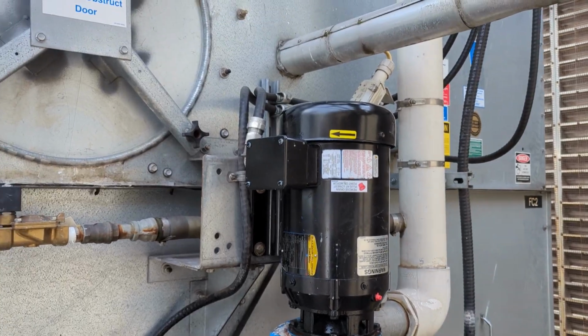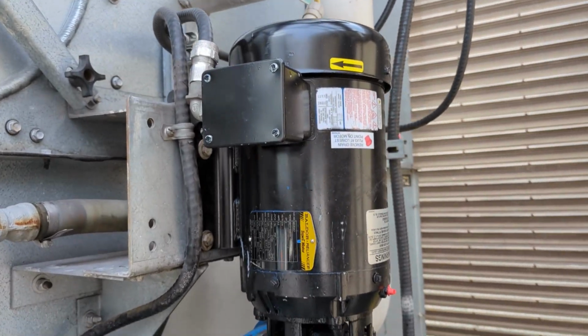We also got back to the cooling towers we were working on last week. This week we replaced one of the water pump motors on cooling tower number 2 because its water seal had been compromised, so it was leaking water and forming calcium and lime deposits on the housing. Also the bearings were really noisy, so we got that replaced.